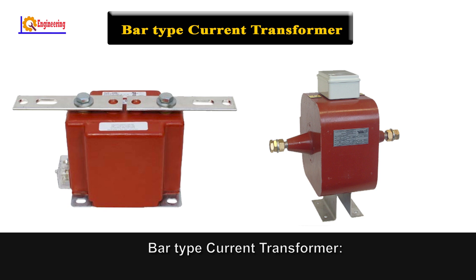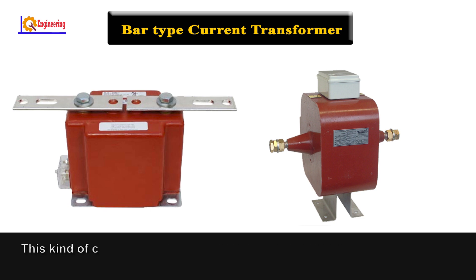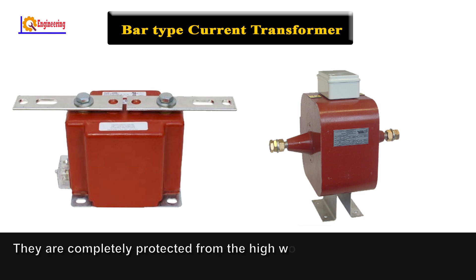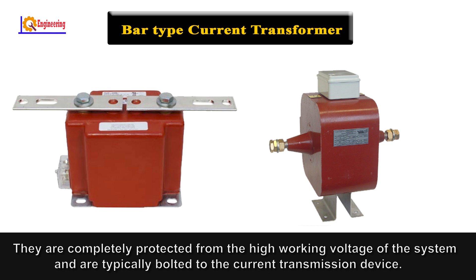Bar type current transformer: This kind of current transformer utilizes the actual cable or bus bar of the main circuit as the primary side winding, which is equal to a single turn. They are completely protected from the high working voltage of the system and are typically bolted to the current transmission device.